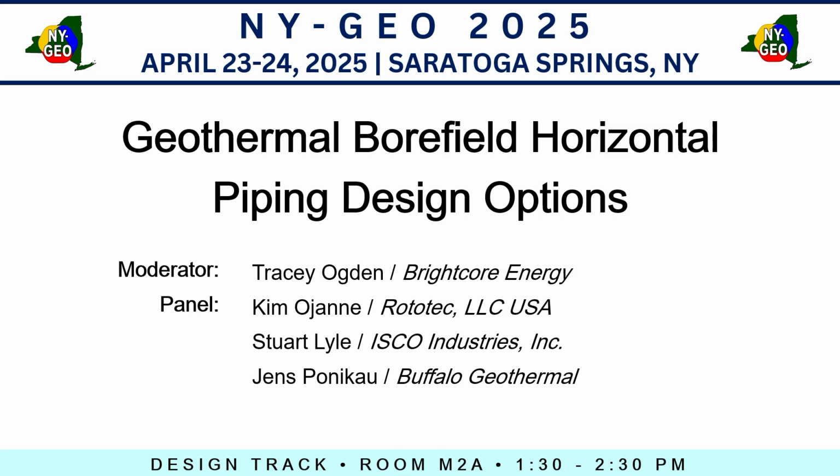Yeah, we protect, if we run across a sewer line or a water pipe or something like that, we certainly want to protect it from freezing. It depends a little bit on your design temperatures. Again, this is multi-family, and Sweden is a different climate. You were probably a little more cooling dominated than we are, although I'm not sure how that affects South Sweden. But you saw the loop flow temperatures, for example, it runs down to 40 degrees, so I'm not concerned about that, and we actually don't insulate for that reason. Even if they run much colder, it depends on how much you're running together in one trench. If you really pack them up, that becomes a large source of coldness in a certain way.